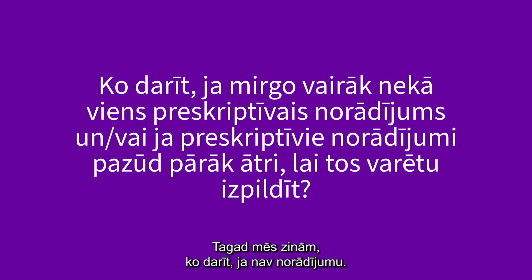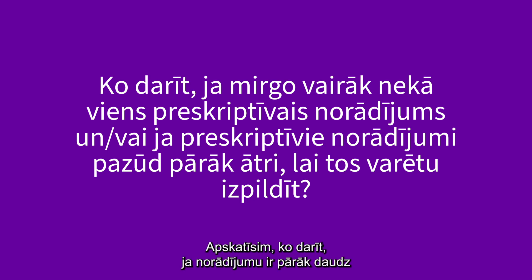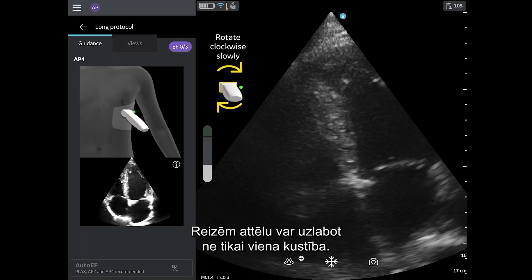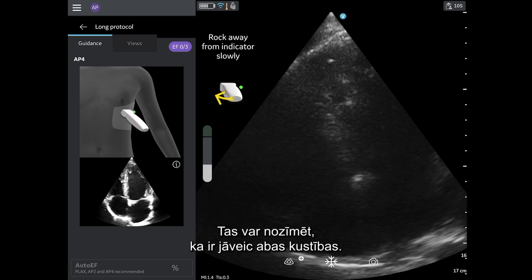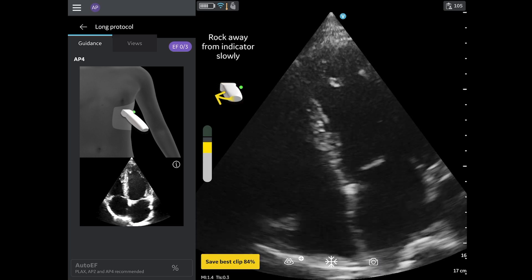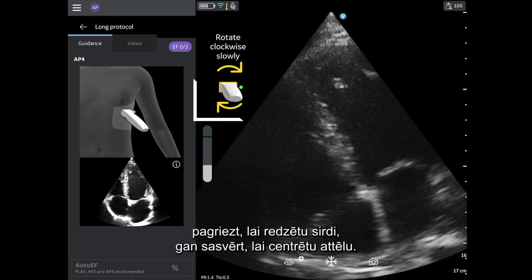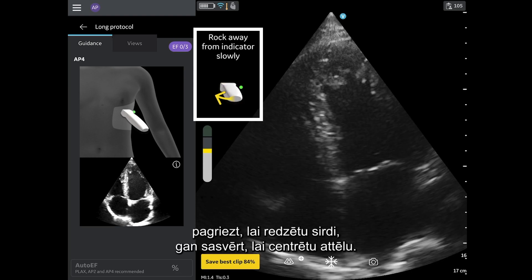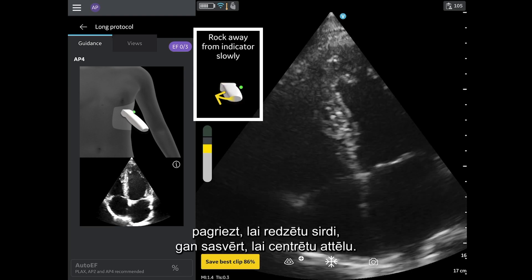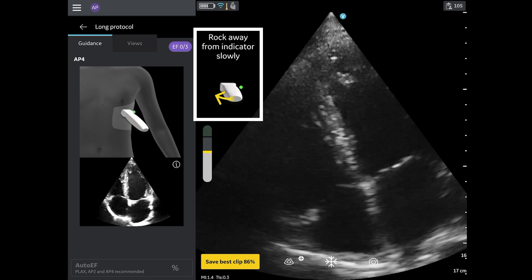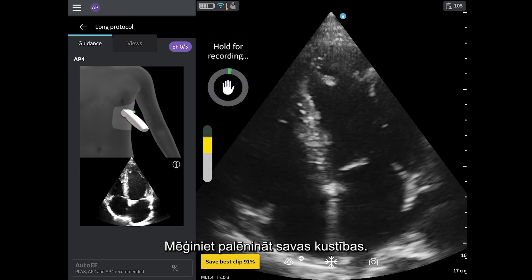Now that we know what to do if there is no guidance, let's review what to do if there is too much guidance, or it disappears too quickly. Sometimes more than one movement can improve the image, meaning both movements may need to occur. In this example, the guidance is directing the user to both rotate to see the heart and rock to center the image. Having multiple movements appear may also mean the user is moving too quickly — try to slow down your movements.